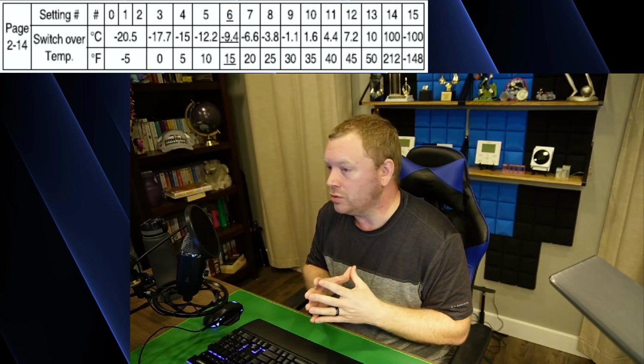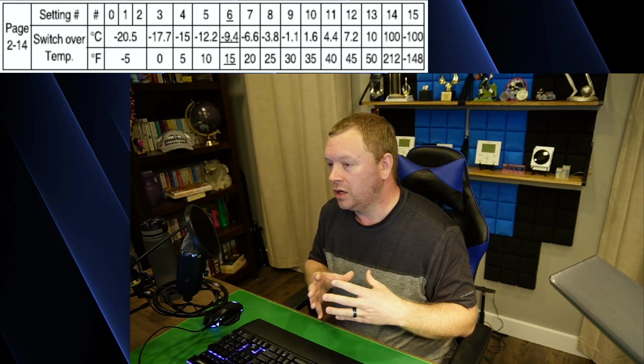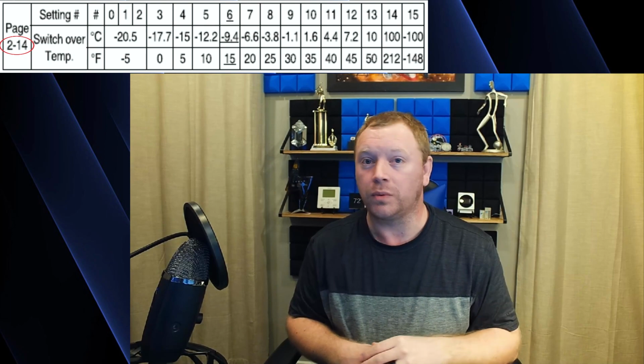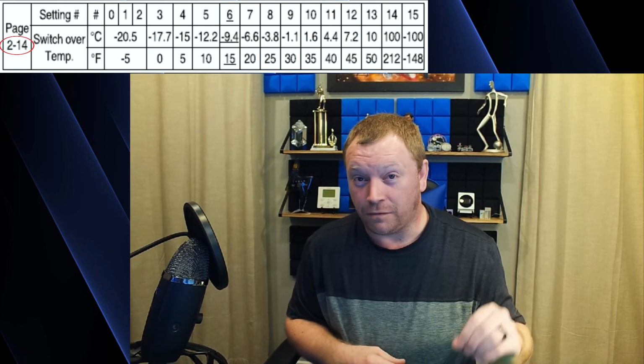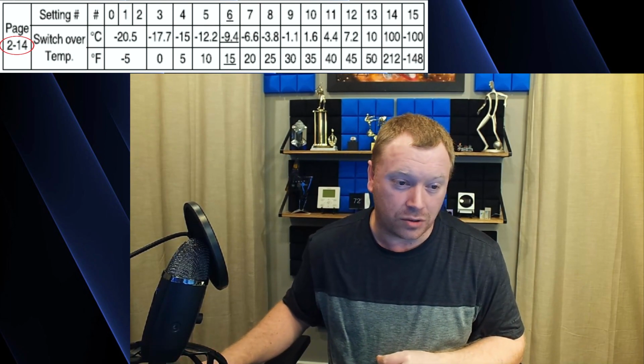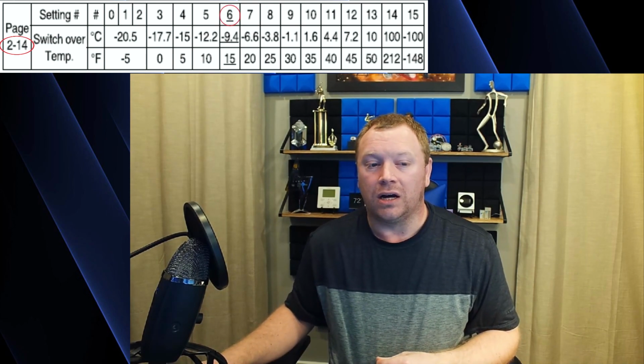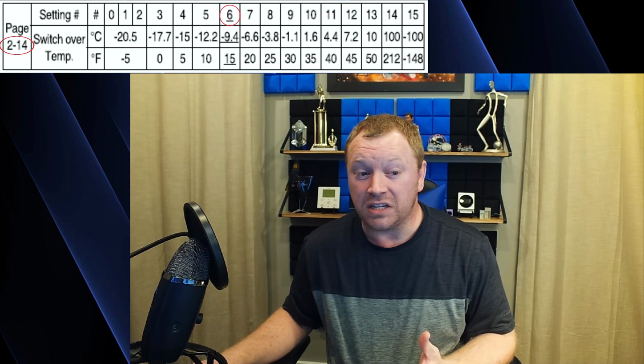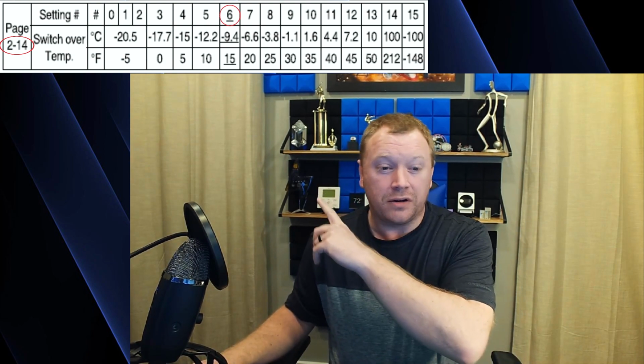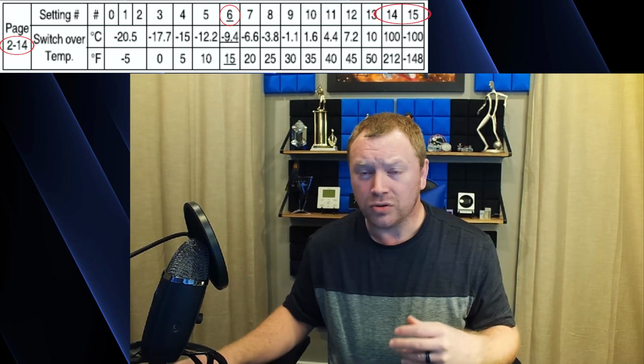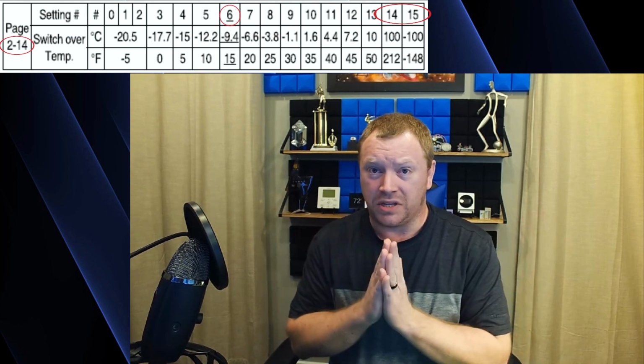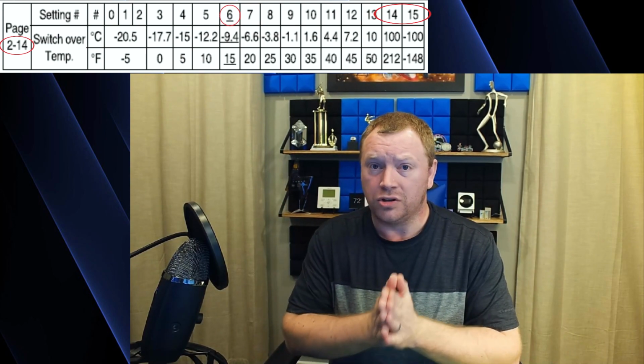So the way that you would go in and change any of these balance point temperatures is you would go to the outdoor unit service mode 2, like we did earlier, and you need to go to setting 14. The default option is going to be option 6. You can change that anywhere from option 0 all the way to option 15. When you're looking at the chart here, you'll see that options 14 and 15 are basically lockouts that either say just run the gas or just run the heat pump.